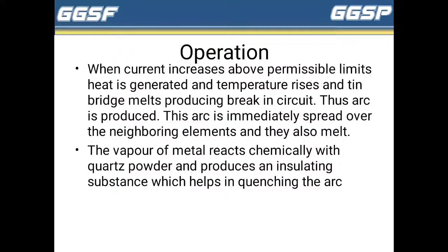The operation of the HRC fuse is like a normal fuse, but the arc quenching medium of the HRC fuse makes it different and special. In the normal condition, the HRC fuse works as a normal fuse, but in abnormal condition, when current increases above the permissible limits, heat is generated and temperature rises. The tin bridge between the contacts melts and a break is produced in the circuit.